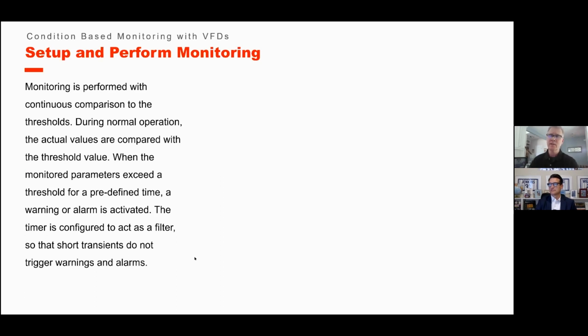And I definitely want to mention the timers involved in this because you have 2 warning timers and you actually have an alarm timer. And what that does is with all applications, you get these short transients of issues that go on. You get spikes in load. If you get a load spike, it's going to affect the winding of the motor, which is going to affect that feedback and that value. So you do have timing things that you can set up to 60,000 seconds. So you can go from, I believe, 1 second to 60,000 seconds. You'll see it on the software when I actually show that. So you don't get any type of faults triggering or transients.